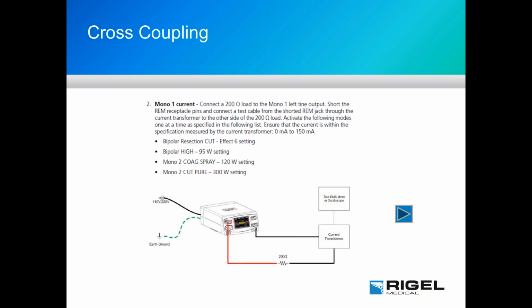And what we want to ensure is that when we energize one of the energy ports, say monopolar 1, we do not have excessive energy coming from any of the other output ports. So an example I was speaking of, if we energize monopolar 1 and there's another surgeon with a bipolar tool, we want to be sure that there is no energy being directed to those forceps. Kind of similar to our high frequency leakage testing, if you will. As far as the current limit, we're looking to have less than 150 milliamps.